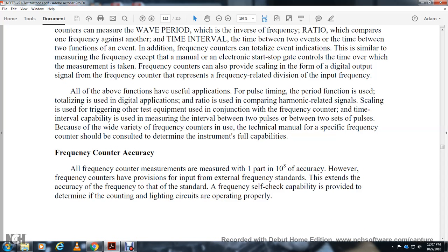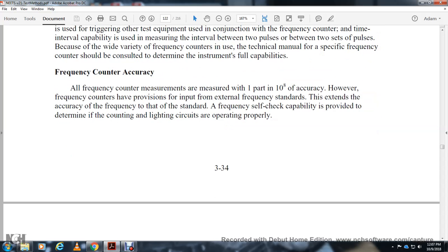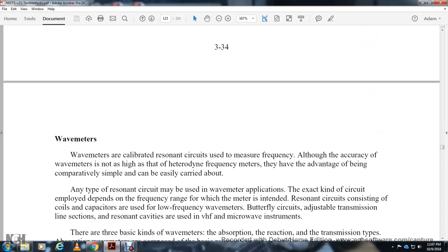All frequency counter measurements are accurate to about one part in 10 to the 8th. Frequency counters have a provision for input of an external frequency standard to extend the accuracy of the measurement. A frequency check with the capabilities provided determines that the counter is operating properly. Wave meters. Wave meters are calibrated resonant circuits used to measure frequency.